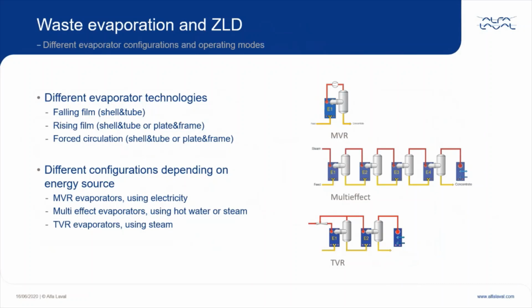In case higher pressure steam is available, a thermal vapor recompression system or TVR can be used to further reduce the steam consumption. Here, the higher pressure of the motive steam is used to compress and recycle part of the vapors produced in the first evaporator to the heating side of this evaporator.